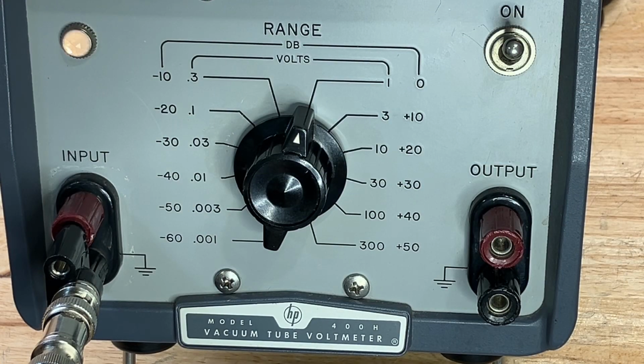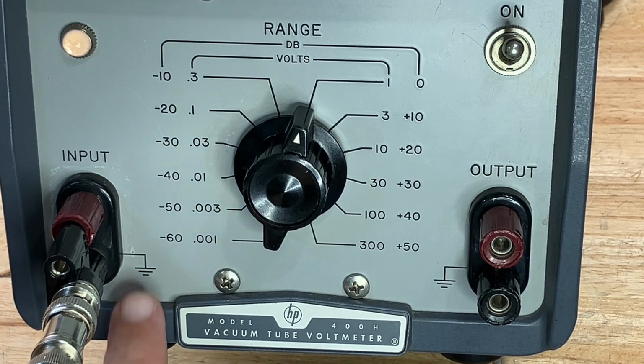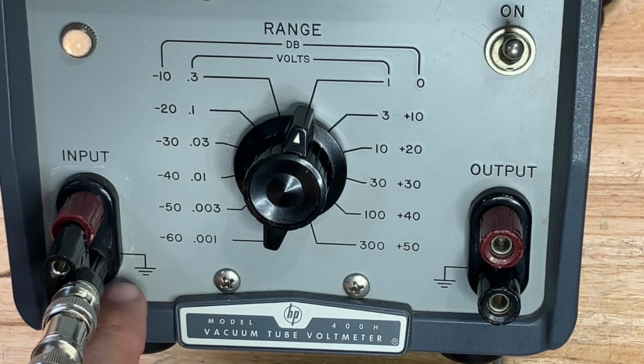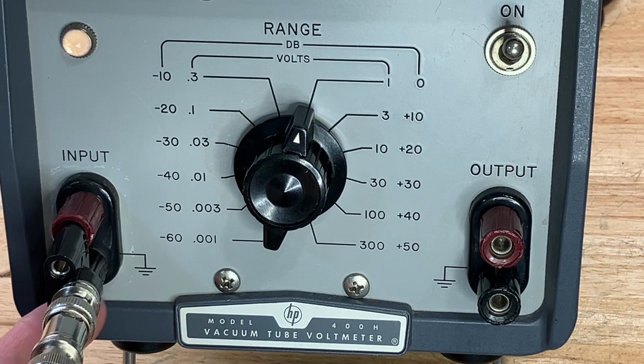One thing I forgot to mention on the HP 400H, and in fact all of Hewlett-Packard's analog AC voltmeters, is that the low terminal on the input is actually connected to earth ground. It's connected to chassis ground, which is connected to earth ground when the line cord is plugged in through the third wire of the line cord. So you cannot make floating measurements with this instrument. It's grounded at the low terminal.